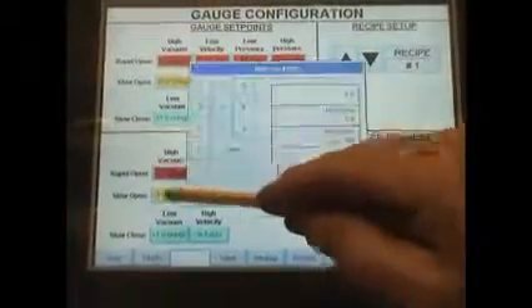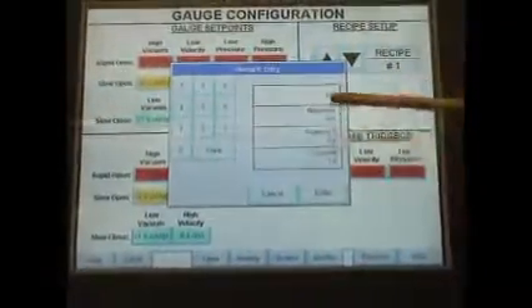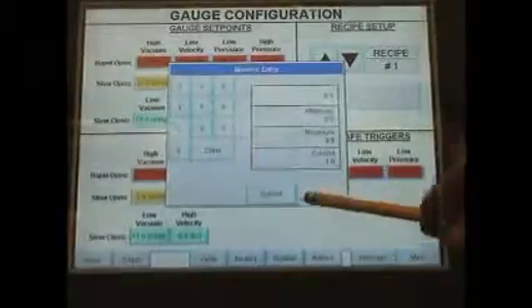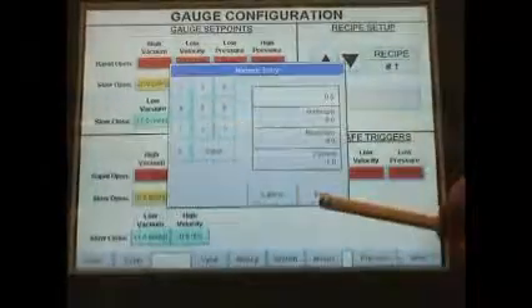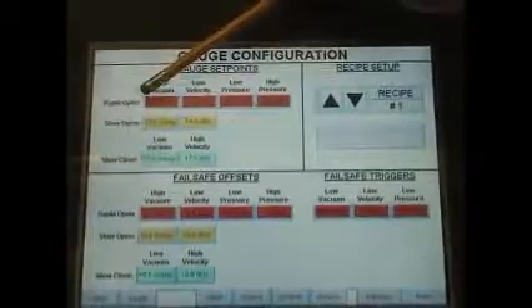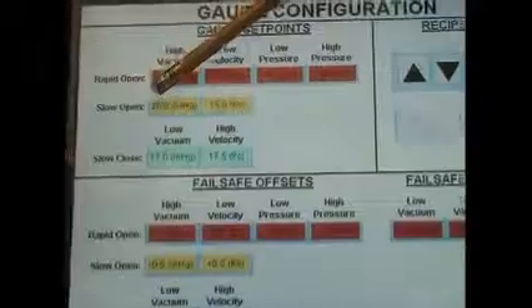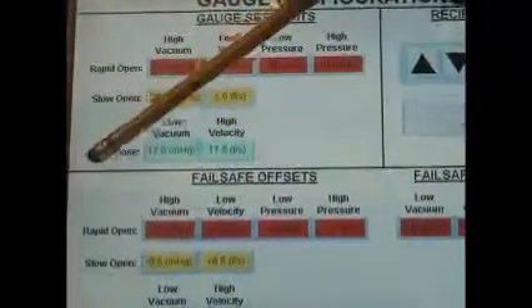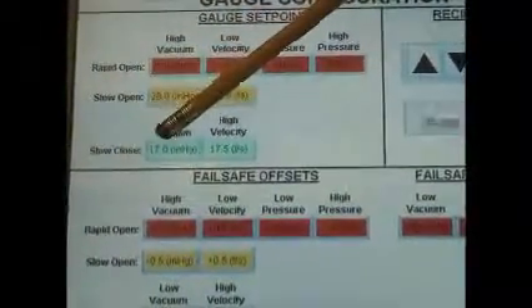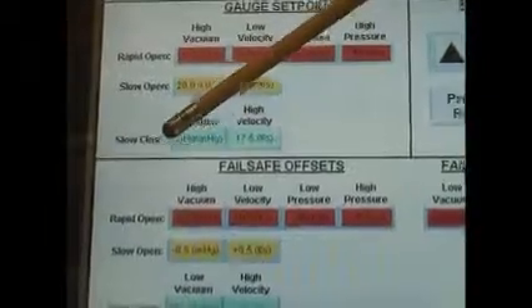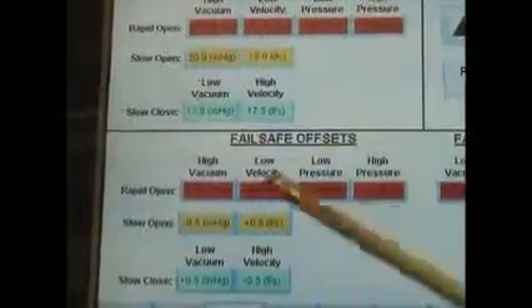Maybe we decide that 1 is too great. So if we would enter a half, for example, in here, on each one of these, then in this case our rapid open would start at 24 and a half, our slow open would start at 19 and a half, and our slow closed, or our green turquoise range, is going to start at 17.5 because we're at a plus here.